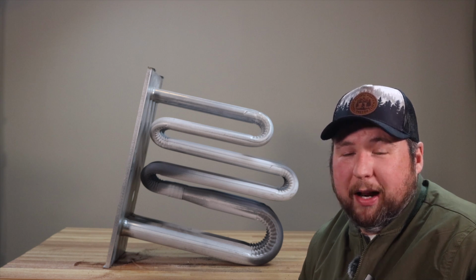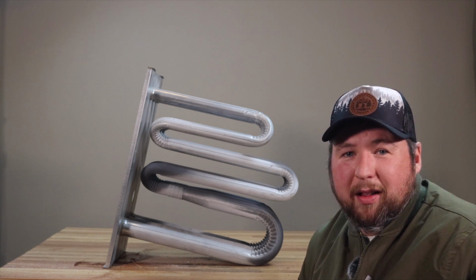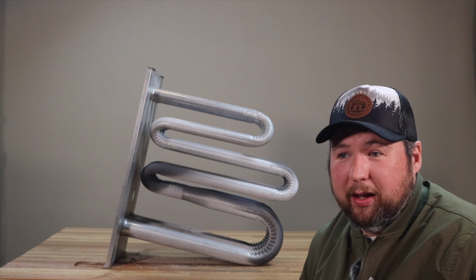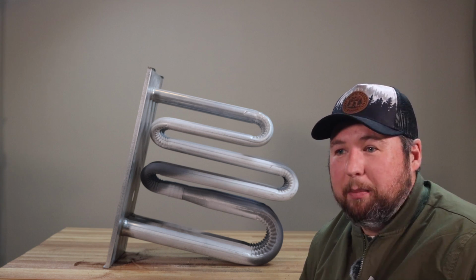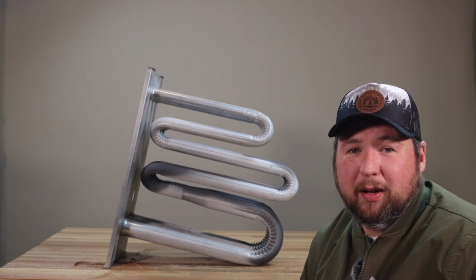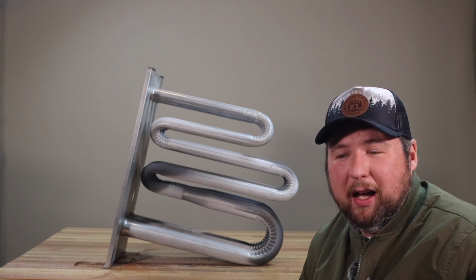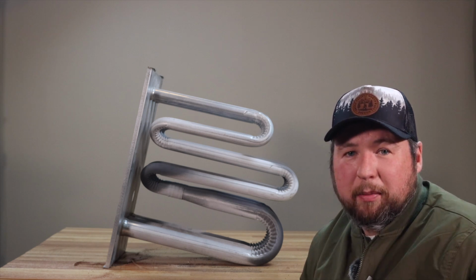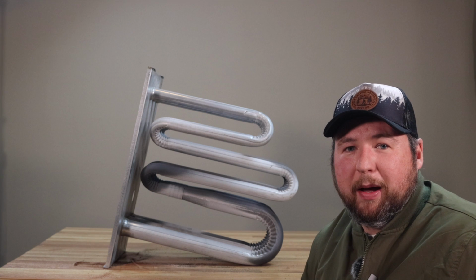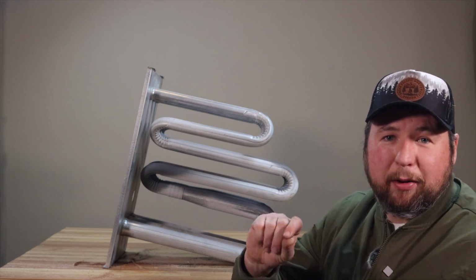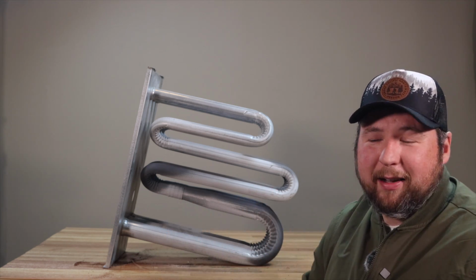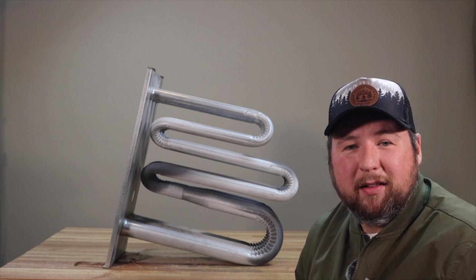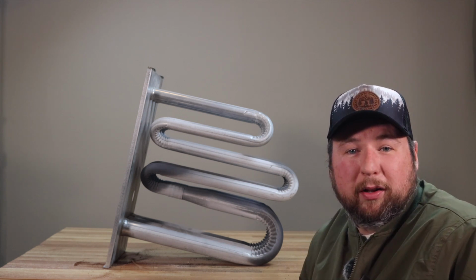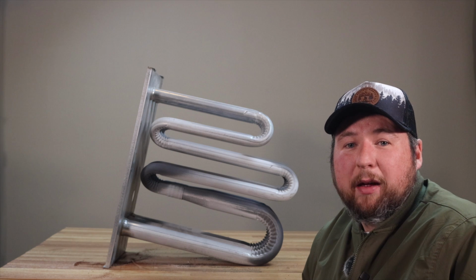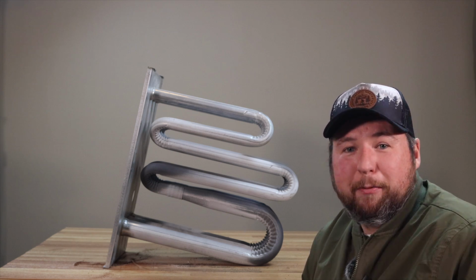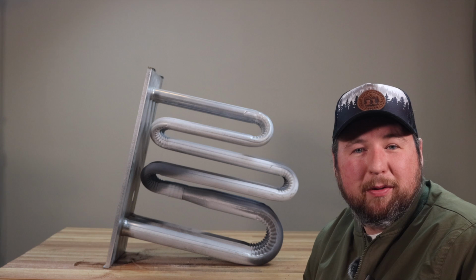I might not turn it off, but I will make sure they are aware that there's a crack in the heat exchanger. It's really tiny, but it's going to get big. I would suggest not running this unit and replacing the heat exchanger or replacing the furnace, but that's up to you. And then they'll say, no, just turn it back on. All right, cool, I told you. Sign right here that I explained to you that it's got a crack. Yep, okay, cool, on my way. Because ultimately you can't force anybody to do anything they don't want to do. But you can make the point clear and put it in writing, get a signature that they know, and you should be good.